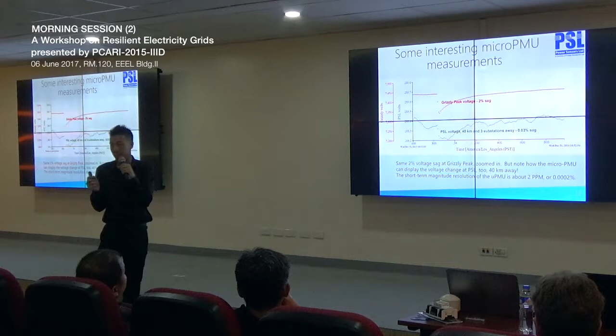Last but not least, here's a classic synchrophasor measurement at Lawrence Berkeley. We have an underground cable about 600 meters long, and when the current went up, we observed an 8 millidegree shift in the phase angle as a result. You could not measure this with a traditional PMU — this was our validation that the micro PMU is capable enough to be used in distribution.